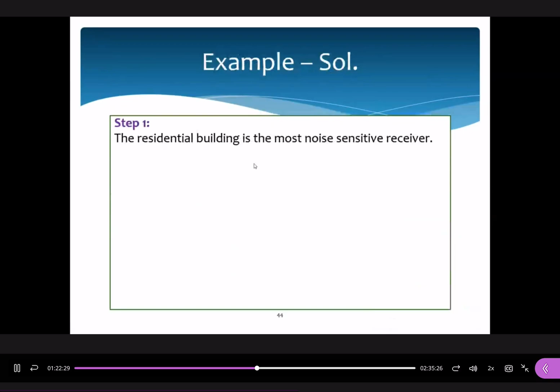Okay, let's check the answer, following all 5 steps. The first step is that the residential building is the most sensitive receiver. The second step is that the sound power level for the power fan is 99 dB according to the table in the document, and the chiller is 105 dBA. You can select this information—the air cooled chillers and the power levels of fans.